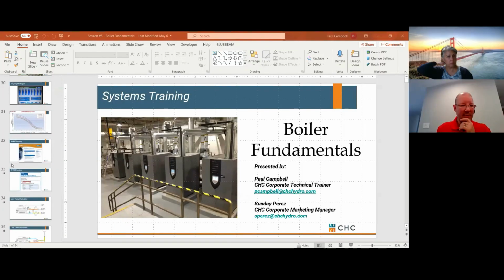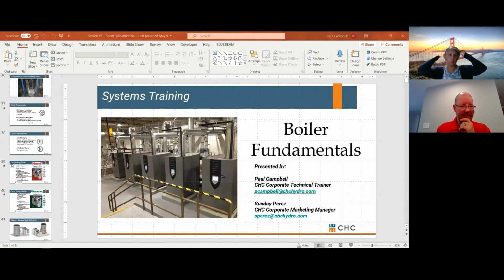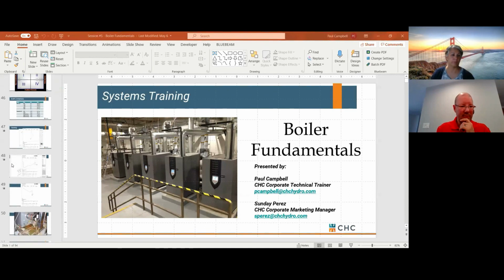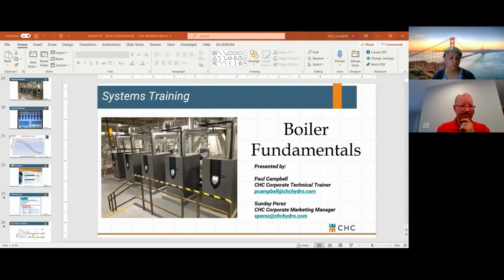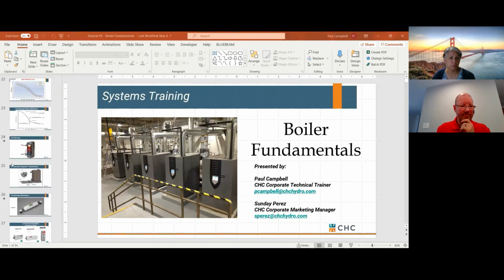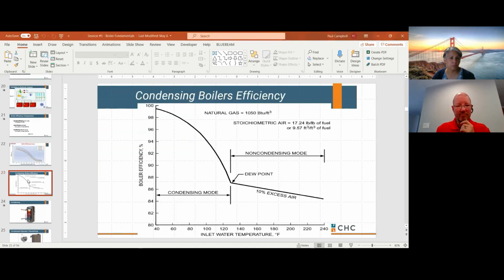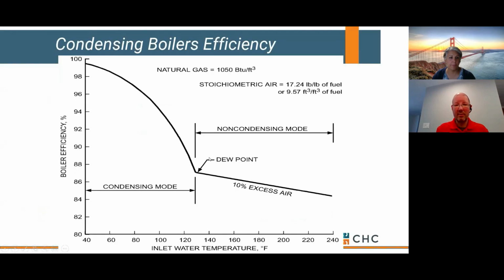And we want to talk about condensing versus non-condensing. Here are my efficiency charts. This might be the best one to look at, and this is a boiler. Are you seeing this okay? Does this work for everybody? Okay, perfect. The thing to keep in mind with all manufacturers, and this is just an ASHRAE chart that's based on return water temperature, but it does show very clearly the difference between condensing and non-condensing.